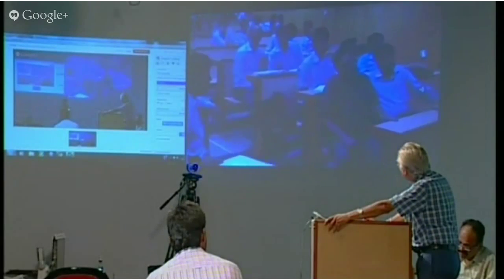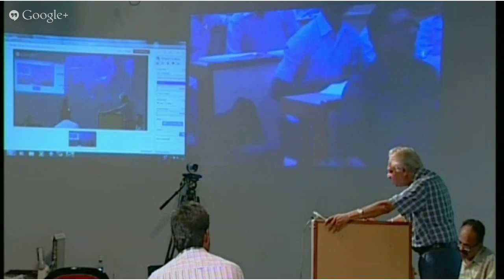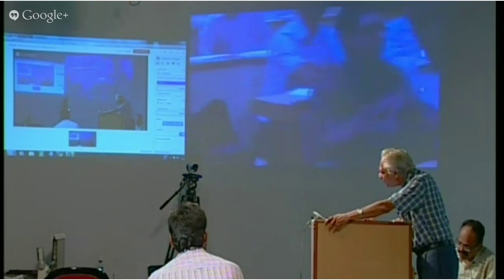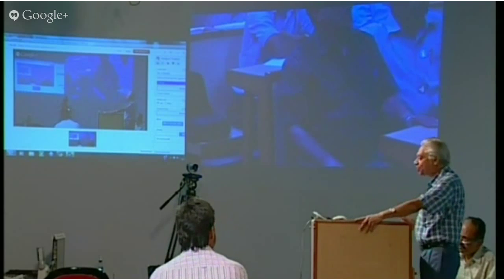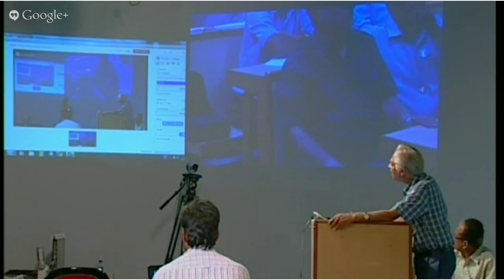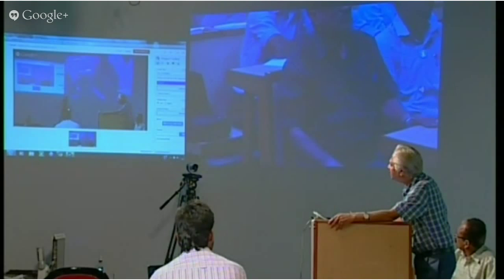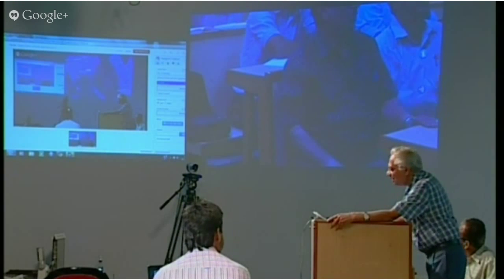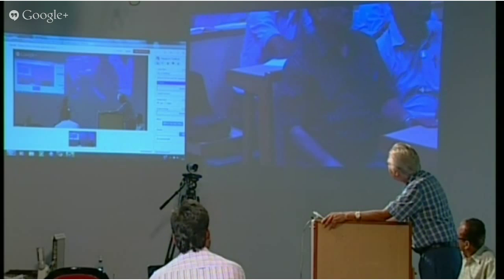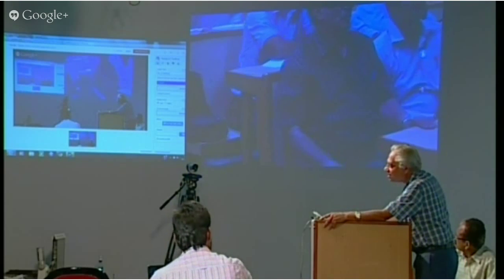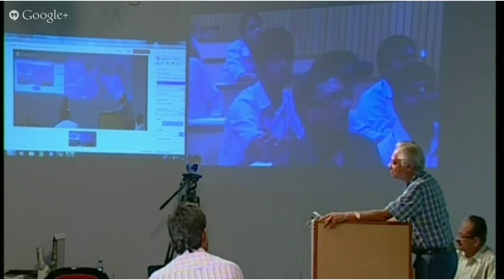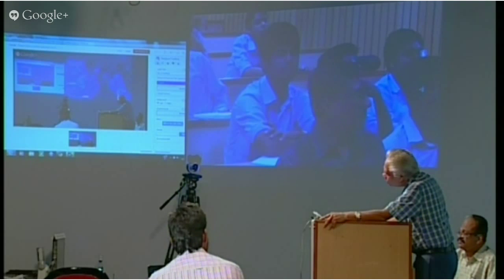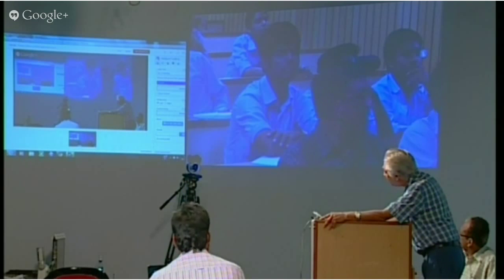Very fine. How can the DC drive be used for mines? Okay. It's a very good question. Well, DC drives are normally avoided for mines because I have forgotten to talk to you within my lecture that mines are very hazardous situations and DC drives are prone to sparks because of commutators. So normally we don't use these drives in mines. We prefer to use AC drives.